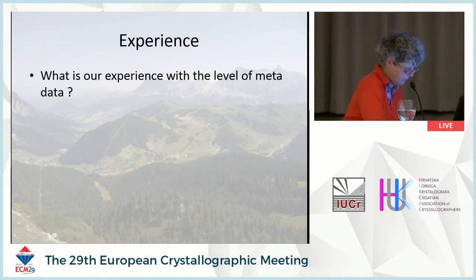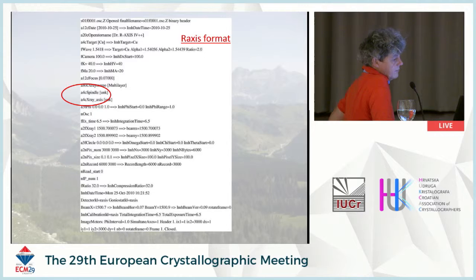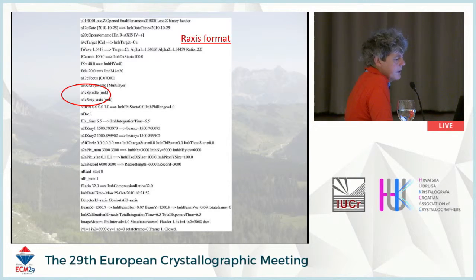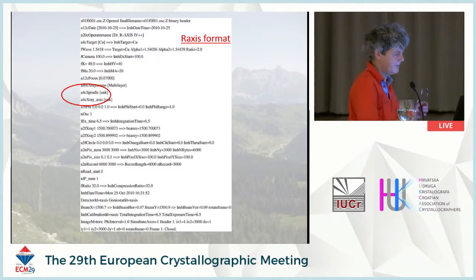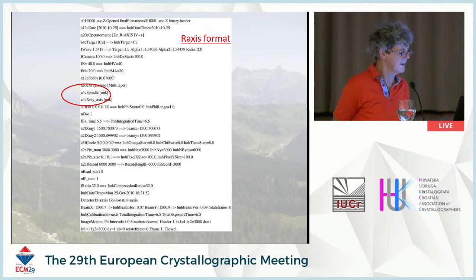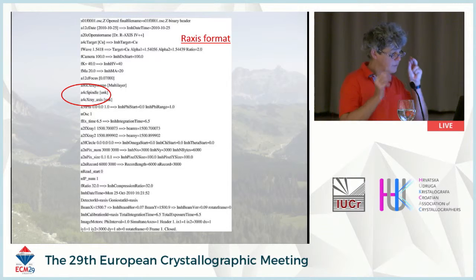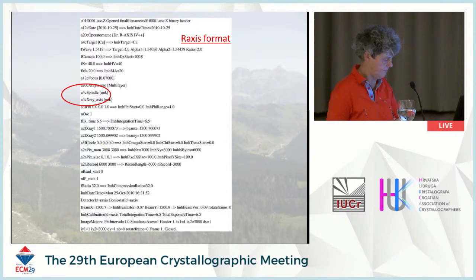What is our experience with the level of metadata? Here is an image header from an R-axis instrument in the Rigaku format. One of the things highlighted is that the spindle axis is actually not defined — it says unknown — and also the direction of the X-ray beam is unknown. This means you have to guess or already know how the setup is.